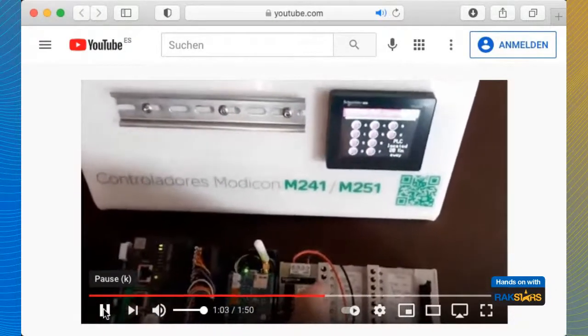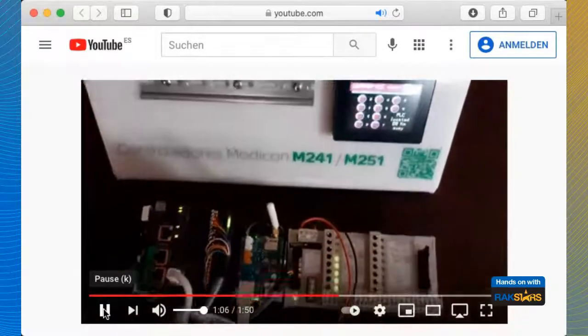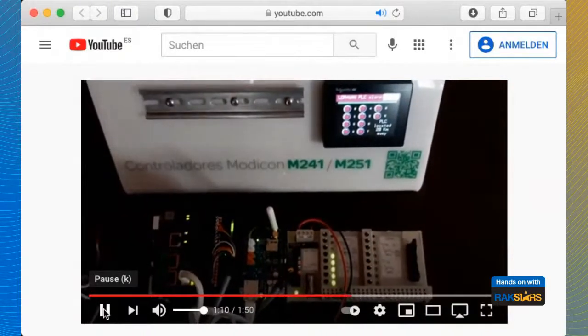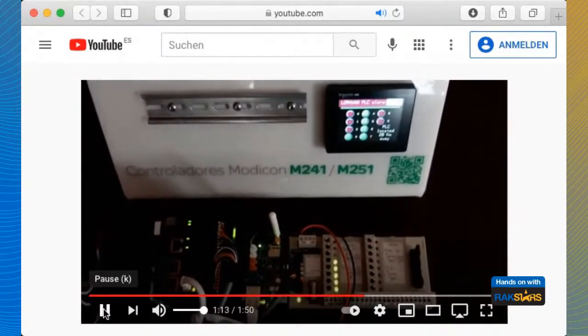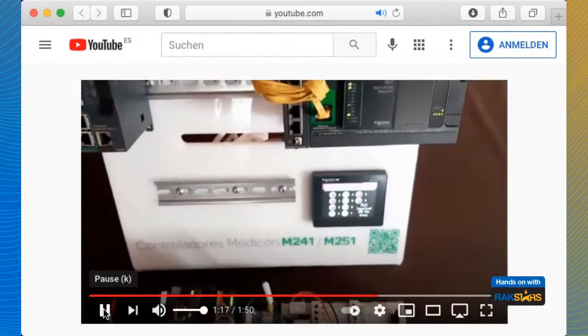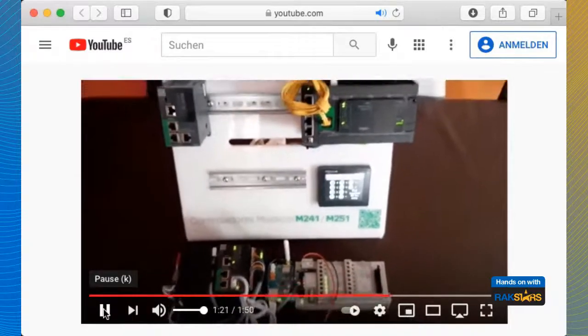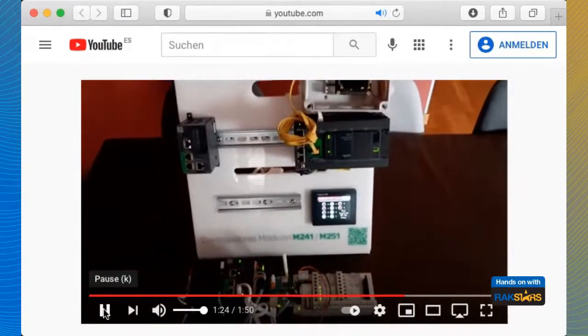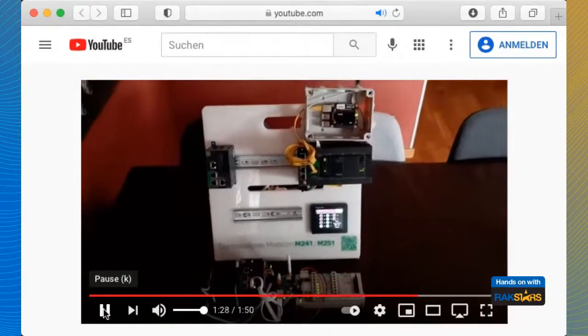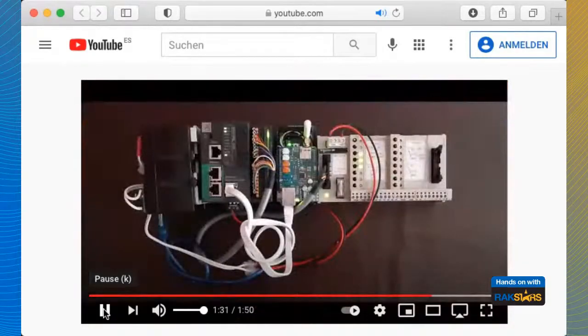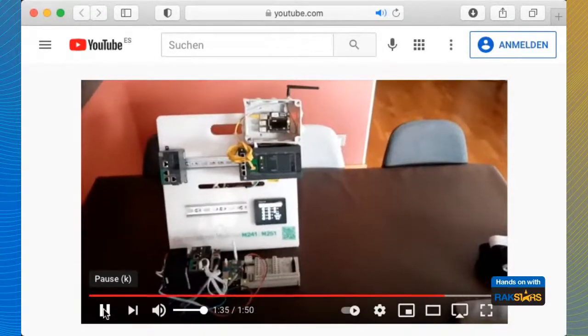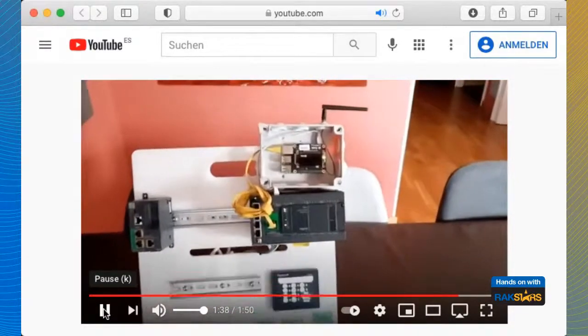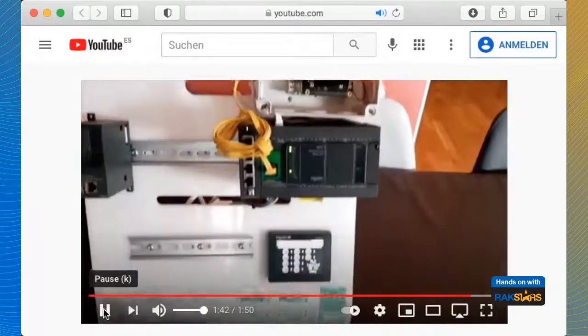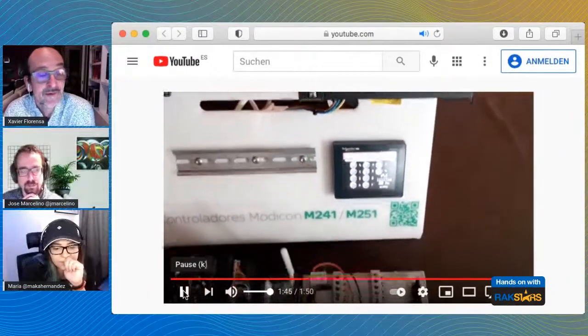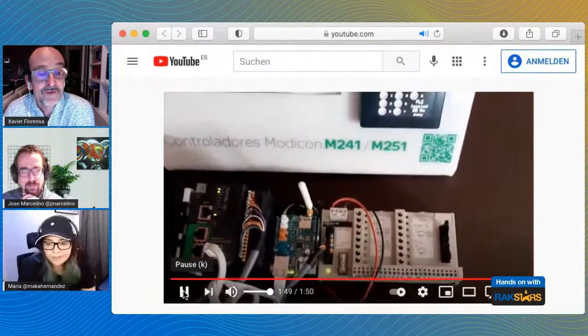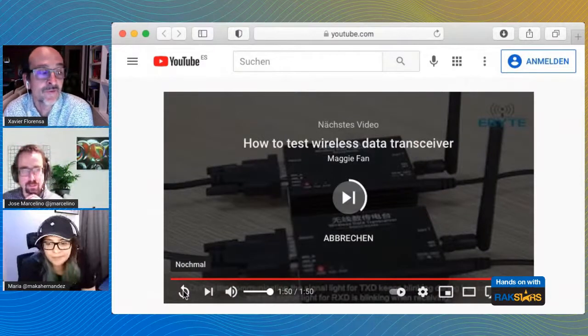Maybe some viewers don't know what a PLC does. Can you say what type of application you would use this type of PLC for? It gets the status of the digital inputs to know, for example, whether water pressure on a water supply pipe is okay or not - if you lose pressure, you get an alarm. Same for air - imagine in a hospital, the air pressure needed for operations and surgery, also the vacuum pressure. If you lose vacuum pressure, you cannot perform the surgery in the hospital. So then you get an alarm because it's a status, on or off, digital input.